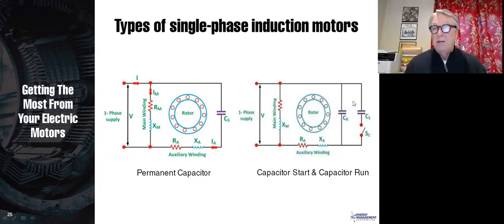Where do these capacitors go? Typically, we like to see the capacitors on the outside of the motor so they're easy to change. It is very, very common to have to change capacitors. Just talking personally, I've got a single phase motor in my furnace, and I've had to change the motor capacitor in that one. That was the only thing that was wrong, the capacitor failed. The same thing in my air conditioner. So these capacitors tend to be the least reliable part and will need to be changed from time to time. If they're not, then the motor doesn't work.